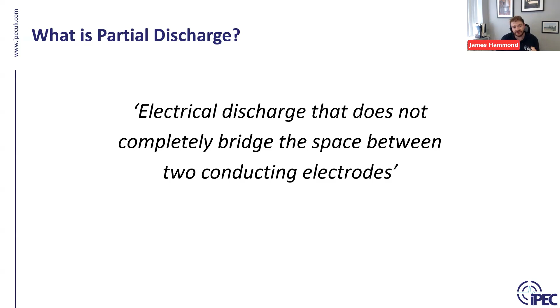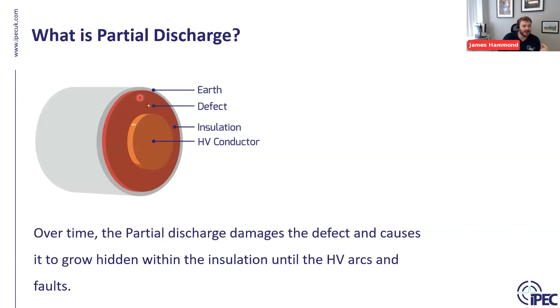And that defect itself, you can see here an example on just a cable. This can be caused at factory. It can be a defect in insulation in the bus bar sections, in cable terminations, any sort of change in medium is how I generally think of it as well. What this defect really does is generate an area of electrical stress concentration. So here's a simplified version of that cable with your HV there, your earth, and a defect. Over time, this partial discharge is happening 50 or 60 times a second, depending on your frequency, slowly damaging, or I should say destroying, this insulation.